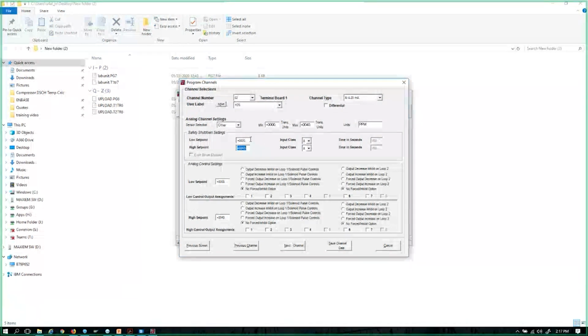In some cases, the customer will say, well, we don't want to shut it down, so we'll simply set the low kill at 0 and the high kill at 400. But they'll say what we want to do is, at 10 parts per million, we'll use a high control set point, and we'll use a spare output. They'll say, we just want to sound an audible alarm and a strobe light in the plant so our workers know to take action. That's a great example of how we would set up a 4 to 20 milliamp H2S monitoring system in the DE-3000.